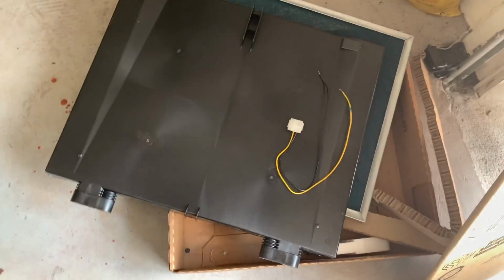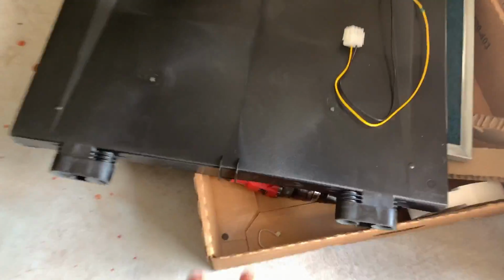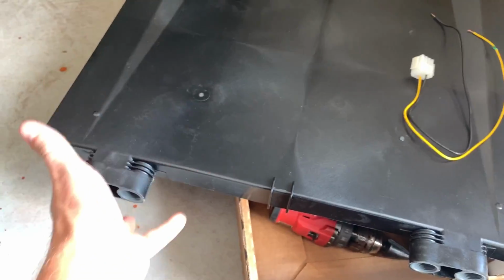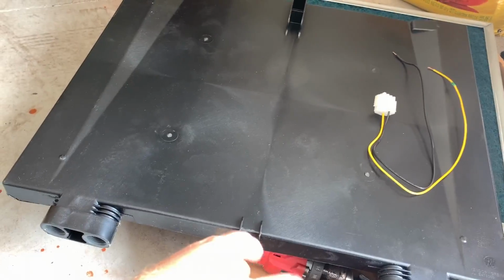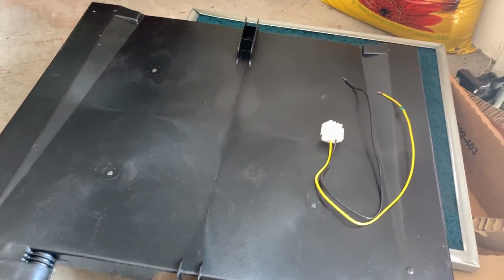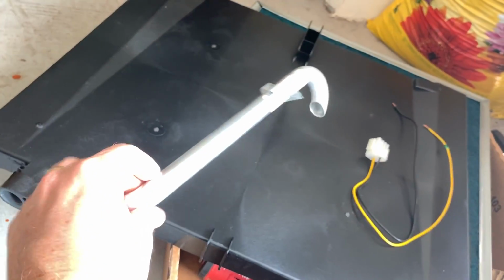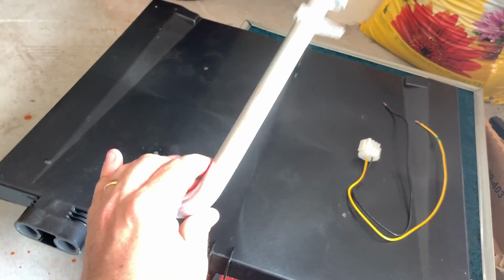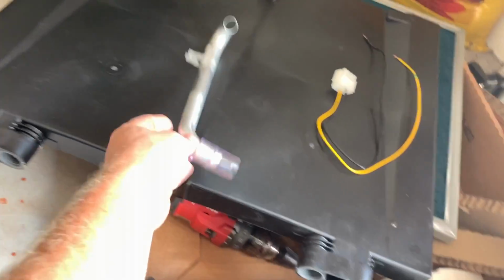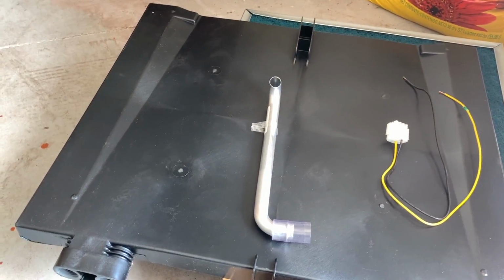Small thing, but anytime we're working on a vertical application, we always remove the horizontal drain pan because it's just another thing that can catch extra dirt and just gets in the way, causes turbulence in the airstream, as well as the little horizontal gooseneck. I mean, does it make a big difference? No, but getting it out of there in a vertical application just is another reduction in turbulence.